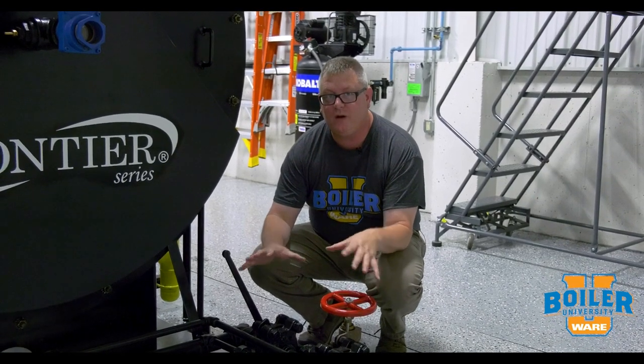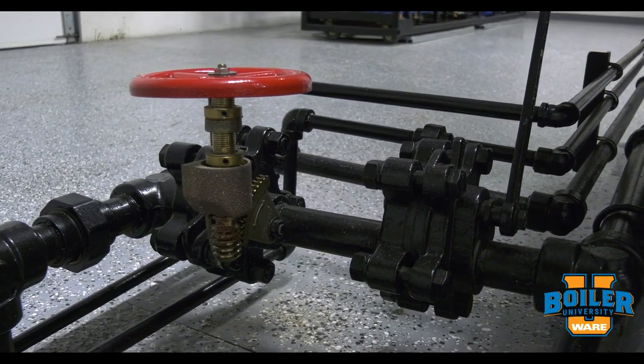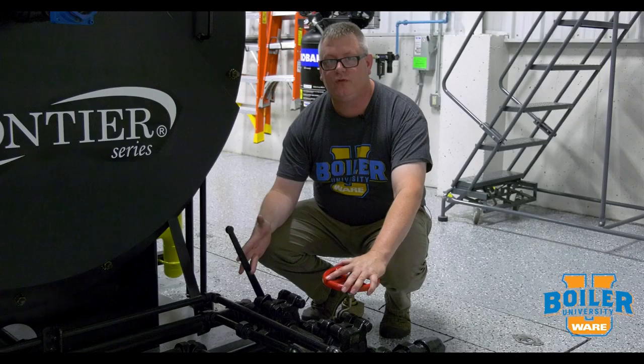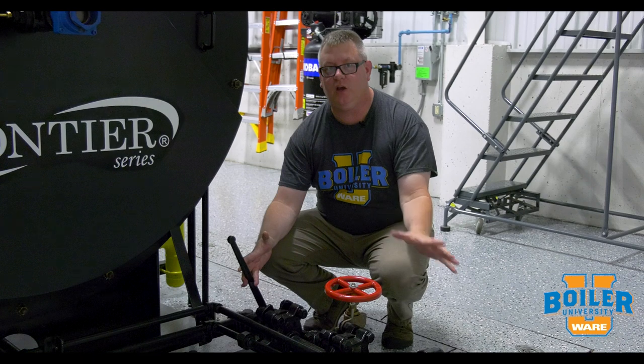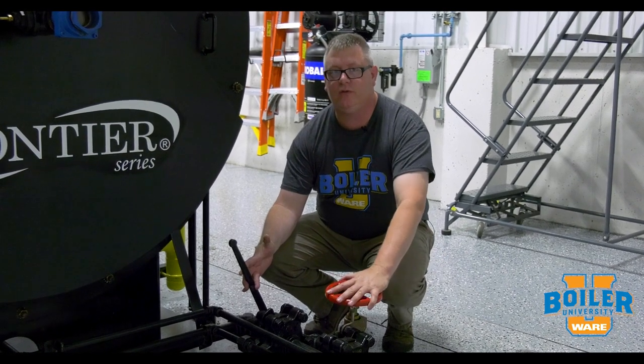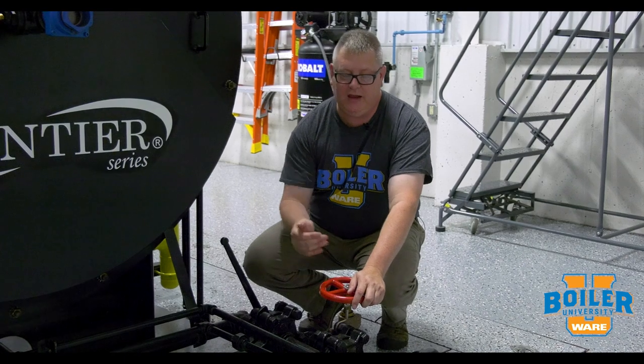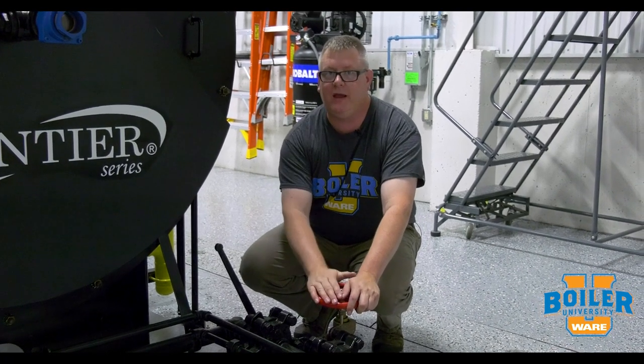On this week's boiler tip we're going to take a look at our bottom blowdown valves. One thing that's interesting about the bottom blowdown valves is that we've always got at least one slow opening valve, and that's by ASME code. We use this valve, closing it last, to prevent hammer and shock in the downstream piping.